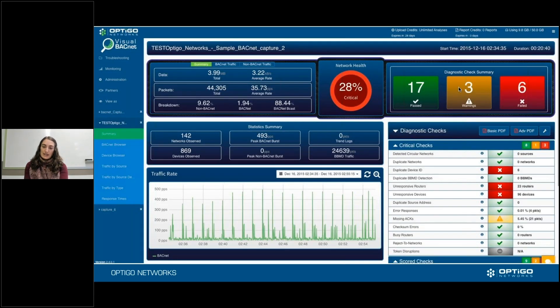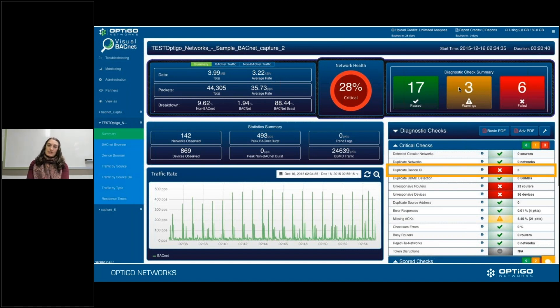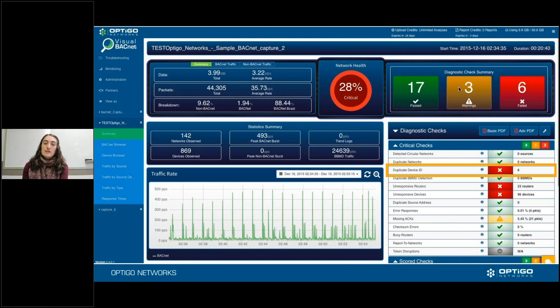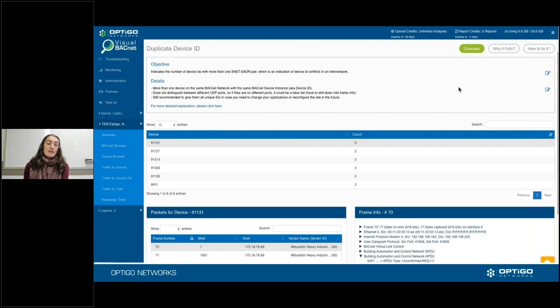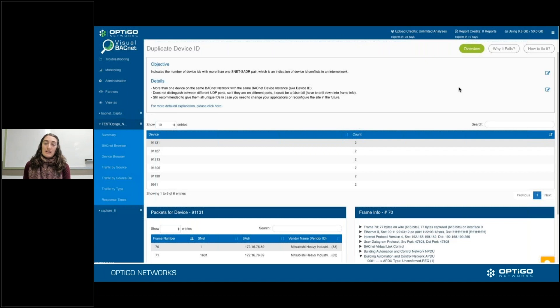Of course, we do have a way to do this in Visual BACnet. If you take that Wireshark file and upload it into Visual BACnet, or you're using Visual BACnet site monitoring, you're going to be able to go to our duplicate device ID diagnostic check. In this case, you can see that we've identified six of them. Our diagnostic checks are put in order of criticality, and duplicate device ID is really high on our list of critical problems. If you click into that in Visual BACnet, you get information about exactly which device ID is duplicated — and we also come across triples and quadruples. As you drill down, you're able to see which subnets it's on. In this example, we have six devices on two different subnets — someone just copied all the configuration and forgot to update the device IDs.